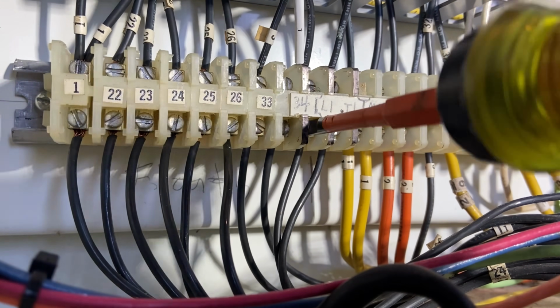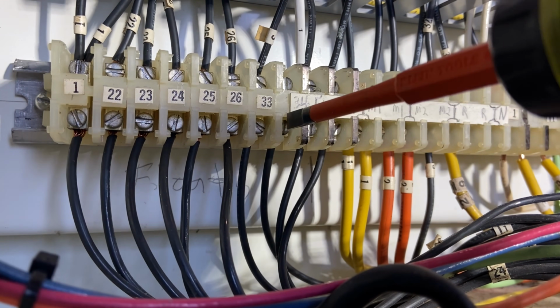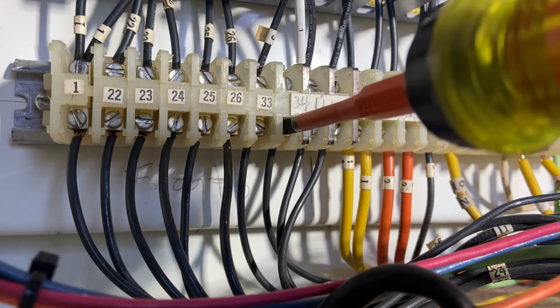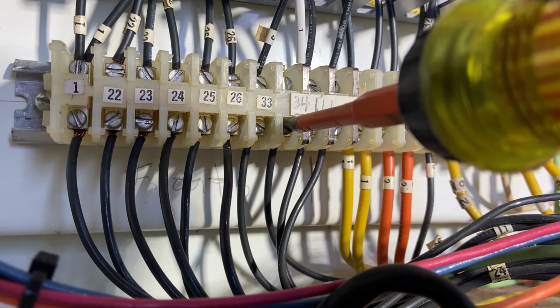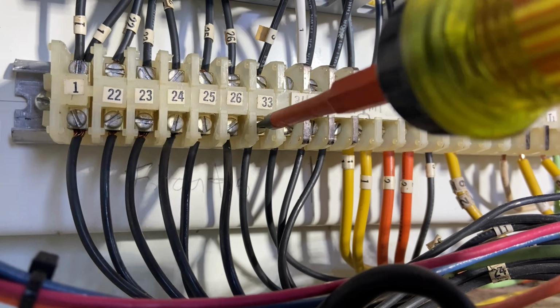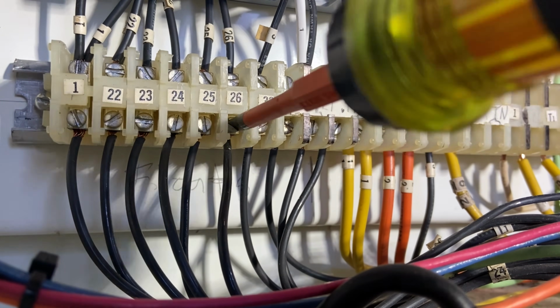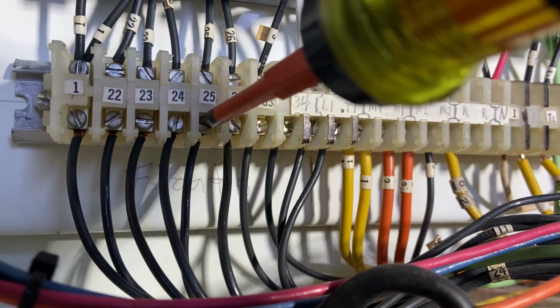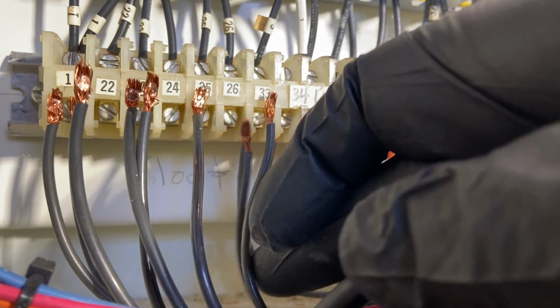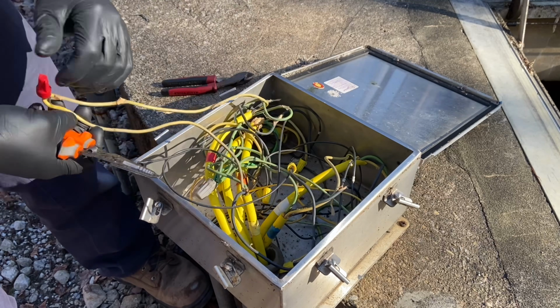And speaking of the low level float, it goes to that relay that I just swapped out. And I swapped it out because if the low level float is not made, neither system will work because it thinks the pump's pumped too far. So I put that relay in and I latched it closed. That way we don't have to worry about it while we disconnect all of our float wires. Everything will keep running in primary. At least that's the idea.